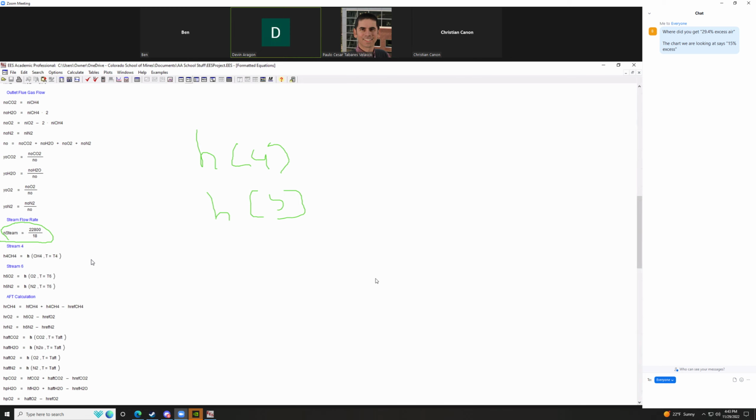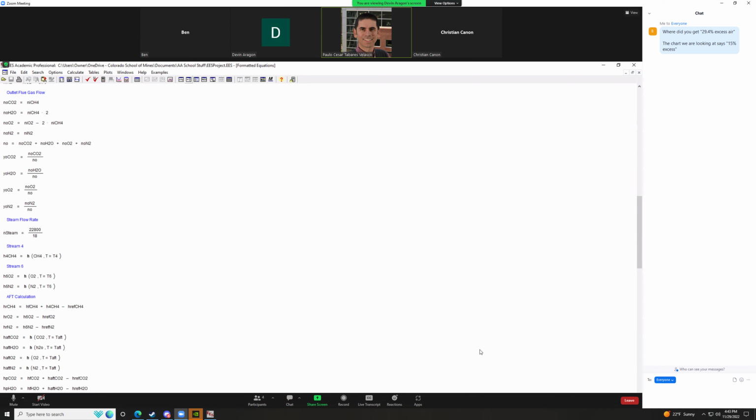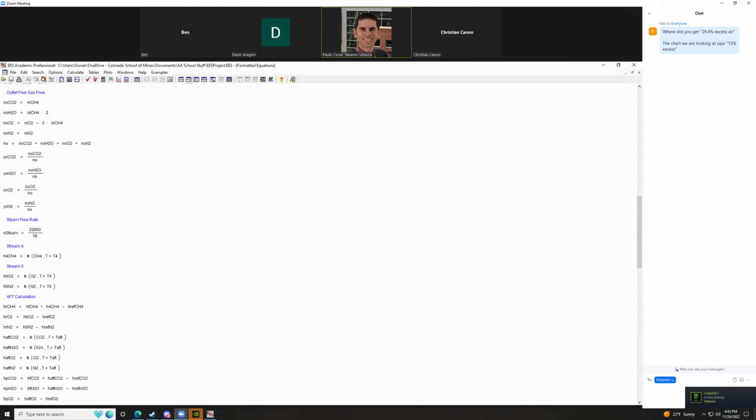Okay, that sounds good. Thank you. We'll definitely try to make those adjustments, make this easier to decipher, and compare two values right on that part. That way it's easier and faster to see what's going on. Right, definitely. But what I'm thinking is, maybe your mass flow rate may be too high. That was driving things to be too low, because the boiler efficiency should be much higher.